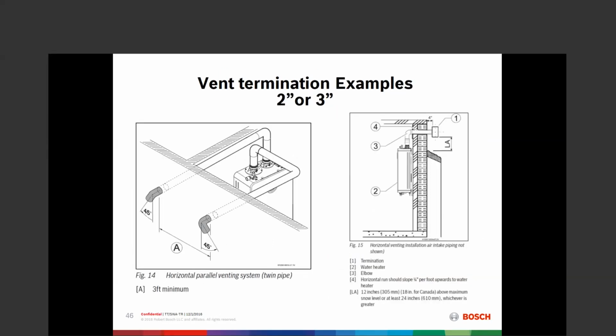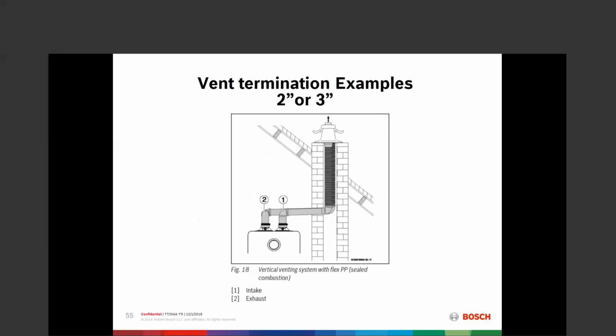If we're in the situation where we can't snorkel and we have to put our intake and our exhaust in the same plane, now we're going to drive ourselves up to 3 feet of separation between the intake and the exhaust. So just be aware of that if you're going to put them in the same plane, we do need 3 feet there. And all of that is to avoid cross-contamination. If we're pulling something other than atmosphere back into the combustion process, that will lead to premature failure of the unit and poor performance.